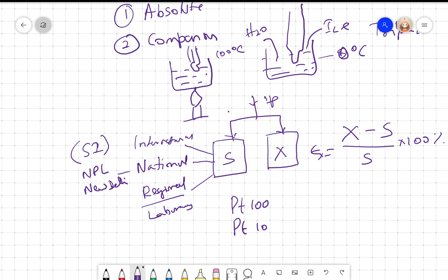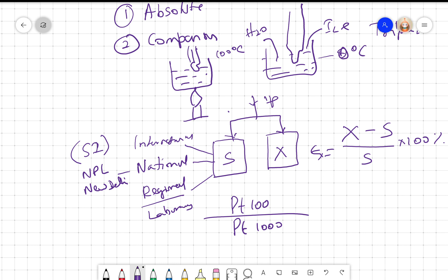For temperature calibration, the PT100 and PT1000 can be used as a laboratory standard. That's what I meant when I said that the PT100 is used as a laboratory standard. With respect to PT100, you can calibrate all other temperature sensors, right? In fact, there are very few transducers that qualify for becoming a laboratory standard, and PT100 is one of them. Okay.